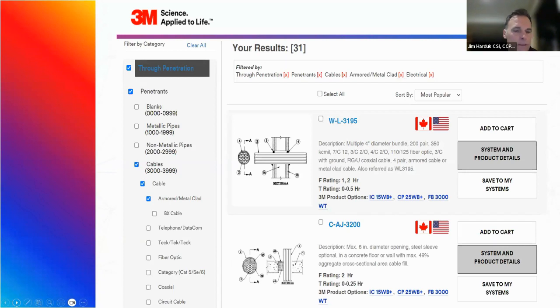So we've kind of simplified this. If you go on the 3M website and you get on the fire protection page, we have a system selection and submittal builder. And this is a screenshot from our system selection guide. So basically, it's a drop-down menu, and you can select what type of fire stop condition you're trying to address, and it'll give you some options for UL tested systems. So when I ran this particular one, I clicked on through penetrations. I identified I was looking for a certain type of cable. In this case, I was looking for systems that had armored metal clad cable in there. Next slide.